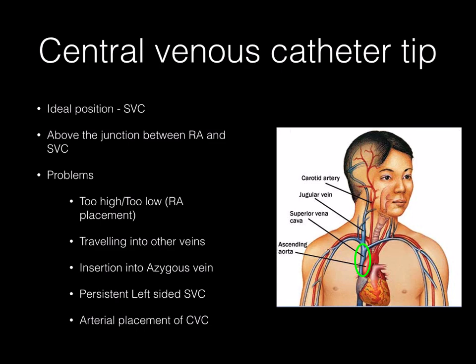And it's very important in these situations to make sure that your catheter is in the right spot by hooking it up to the transducer set, so that what you're measuring is a venous trace and not an arterial trace. In any case, you need to make sure that your central venous catheter is situated in the vein by connecting it to a transducer, as well as maybe doing a blood gas through the central venous catheter. On occasions, you can have an arterial placement of the CVC.